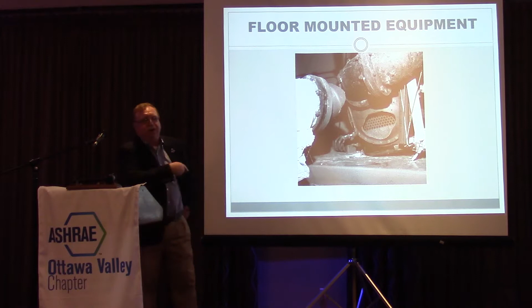The first thing most people think is, oh, I'll get some braided stainless steel hoses. Yeah, they'll hold into it, but they won't move an inch. Braided stainless steel is the hardest of the flex connector series you can buy. Unless you want a flex connector that's 3 foot long, it can't move an inch. You can see these little short ones - oh yeah, you can move an inch, it may be 500,000 pounds of force, but not what you're going to see here, so you never get the movement you're looking for.